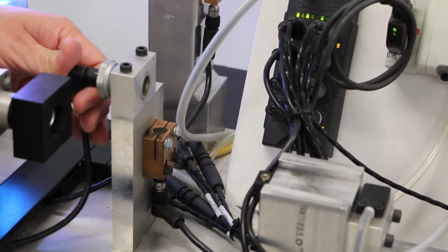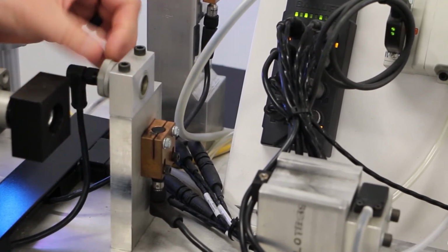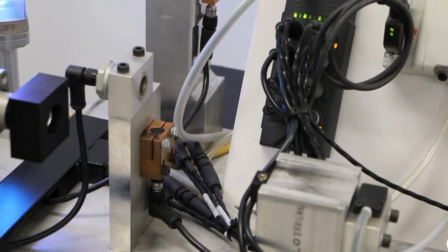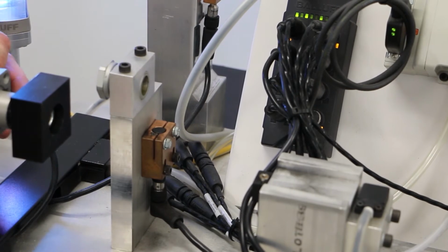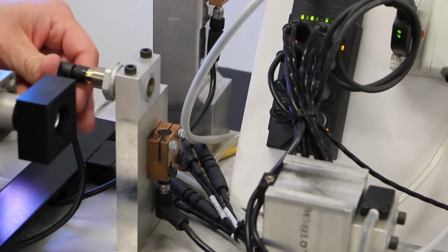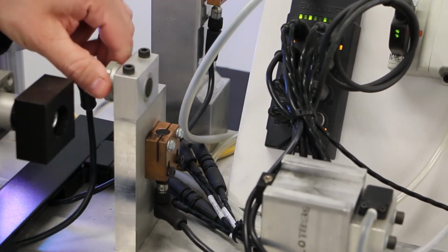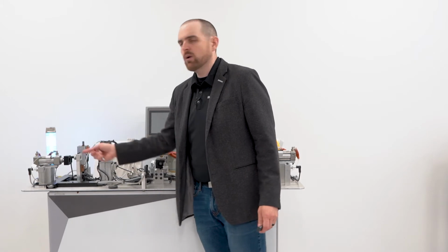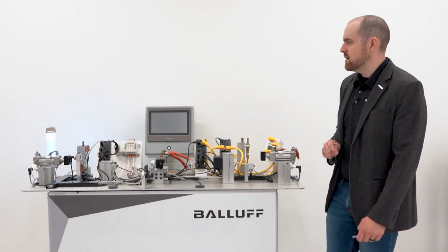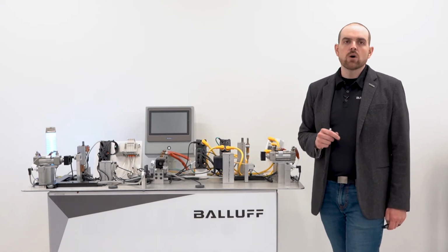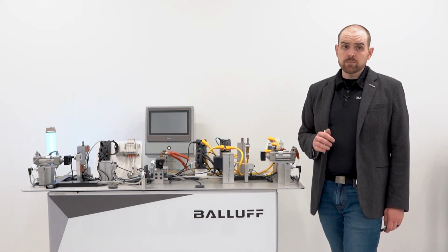And then last but not least, when we're talking about protection, I love the quick change prox mount. Yes, it provides protection. It can be a heat sink for an inductive prox if it's kind of a warm application. But it also has a quick turn nut. You quick turn the nut, you could slide the prox out, you immediately slam in a new prox, you turn the nut, and it's sealed in its application. It's gapped perfectly. No one has to sit and adjust where the position of the sensor is. It's right in the right place every time when you have to change it out. So these are all great protection tools in your portfolio in a welding environment.